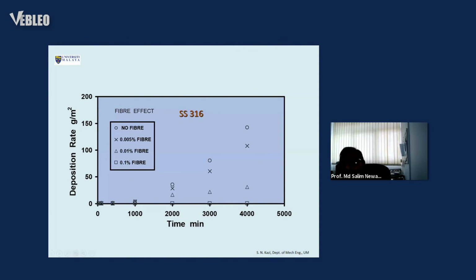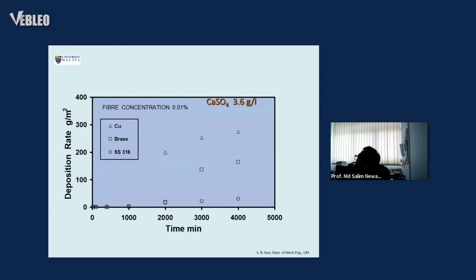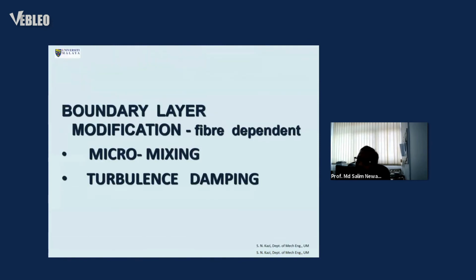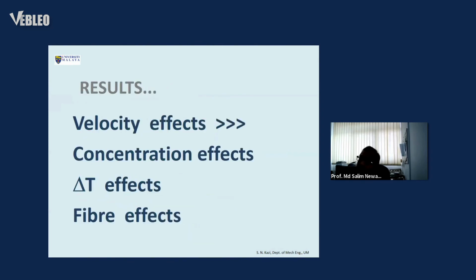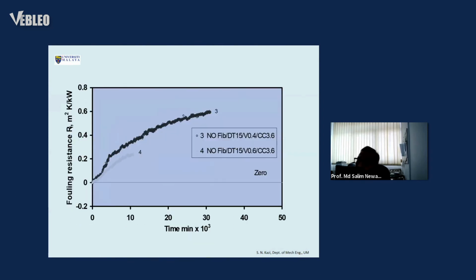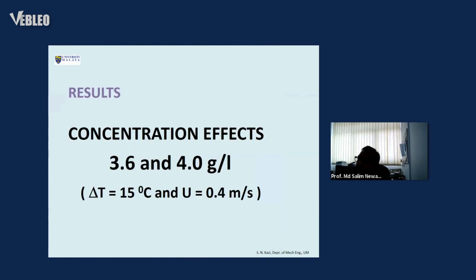If we use fiber particles smaller in size, say 2 millimeter, at a concentration of 0.1% in the solution, we get almost no fouling for a long period of time. At 0.1%, there was no fouling for about 40 days. If the concentration is reduced, we get fouling, but much lower than without any additive in the fouling solution. So this data indicates that it can be used for mitigation of fouling. Different test sections were tested, and in most cases the same results were observed.